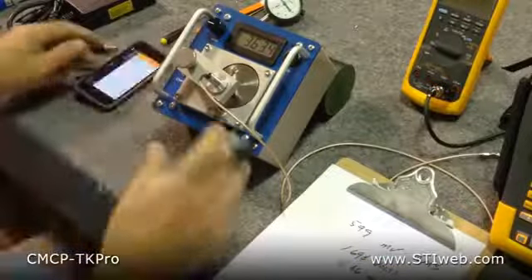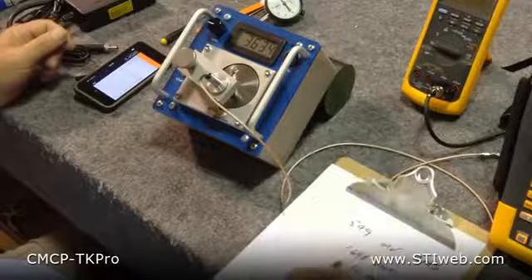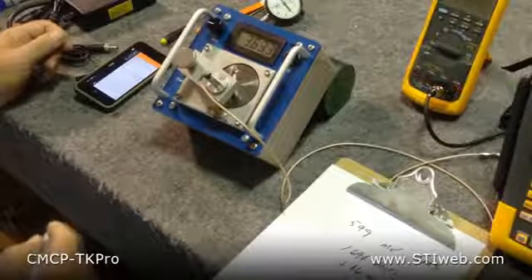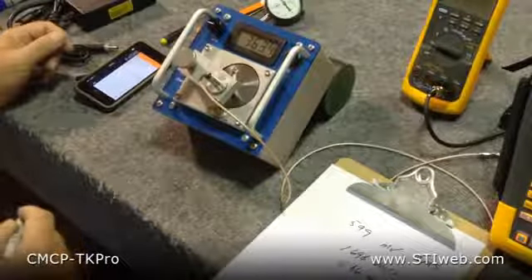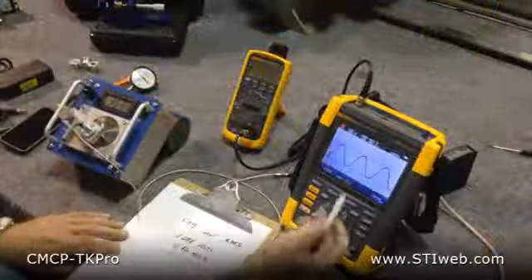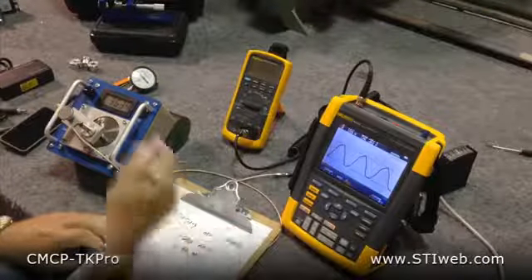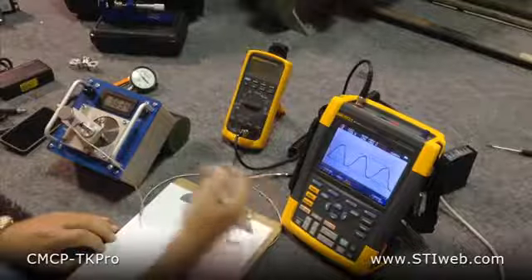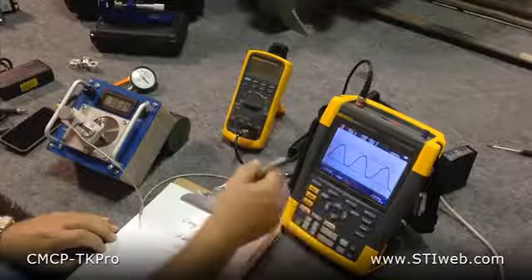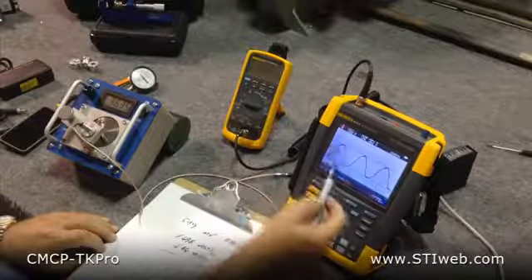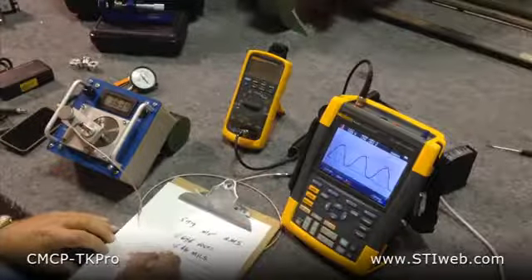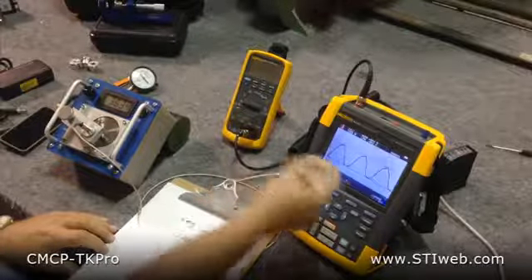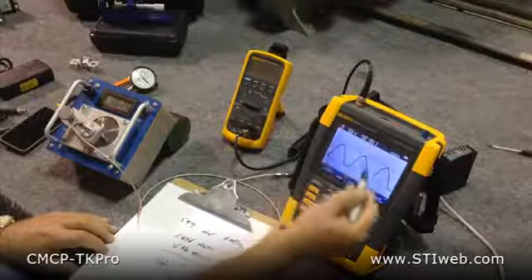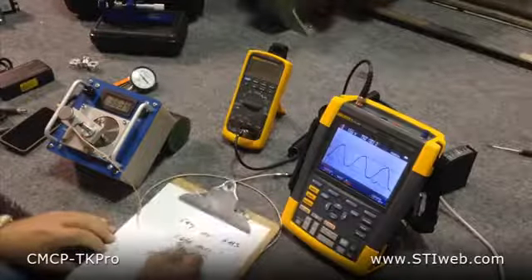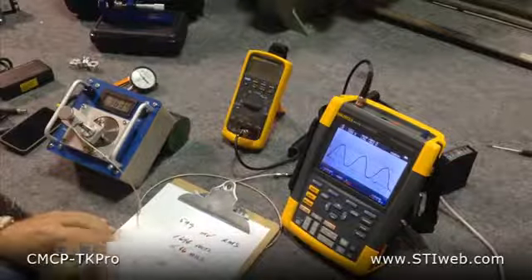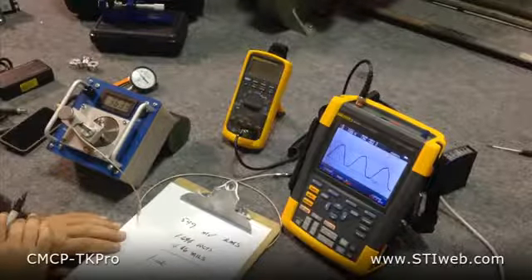So with this running, hooked up to your system at the machine, you go back to your monitoring system. The monitoring system should be reading about 8.5 mils. If you happen to have an oscilloscope, we can look at the dynamic output of the signal directly in the oscilloscope from the driver. You see we set the lines here. We have 1.66 volts on the oscilloscope from the high to the low, and you can see the signal is very sinusoidal. So anyway, we're producing 8.5 mils going into the monitoring system.